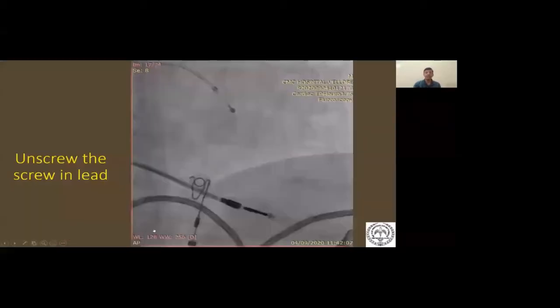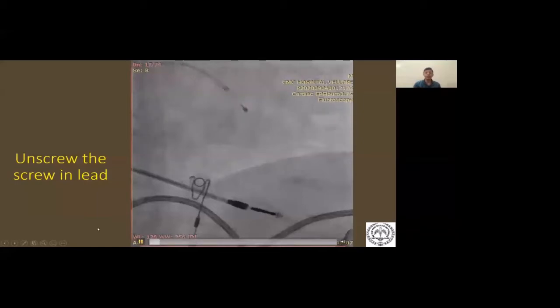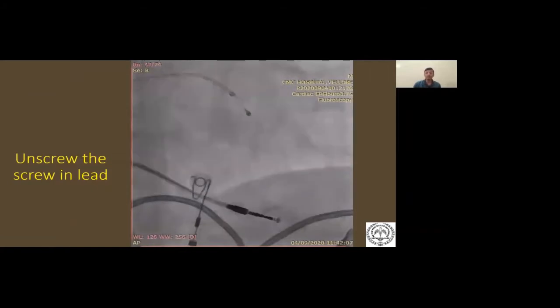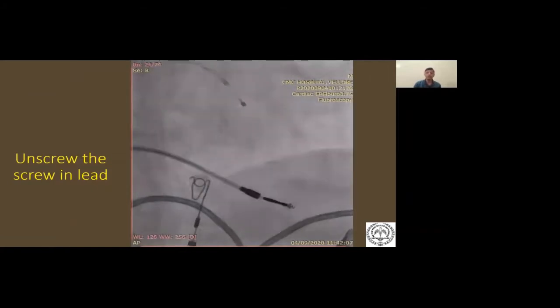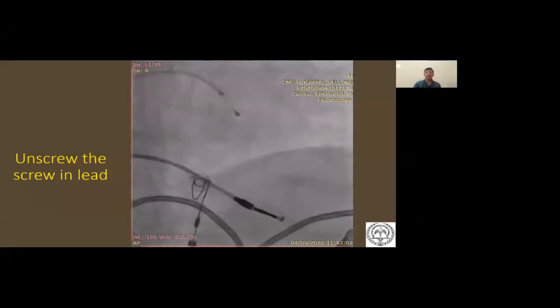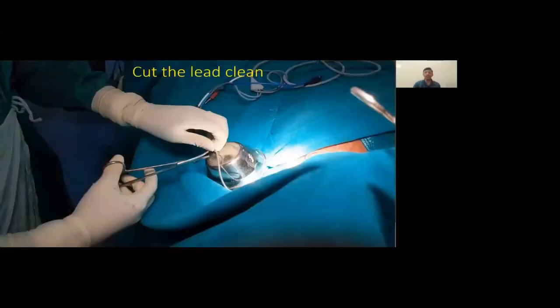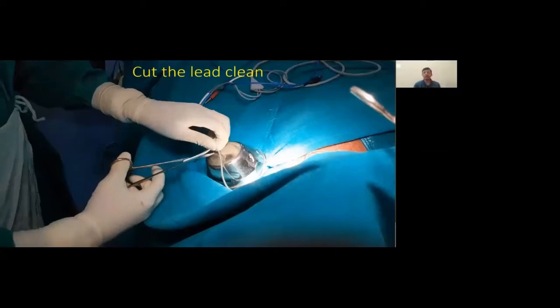Then it's important thereafter to unscrew a screw-in lead rather than start tugging straight away. So always remember to unscrew the lead before you tug it. And then after you unscrew and make sure that the lead has gone in completely, the next step is to cut the lead. And when you cut the lead, you need to cut it clean so that you have a nice circumferential opening through which you need to send in your stylet.